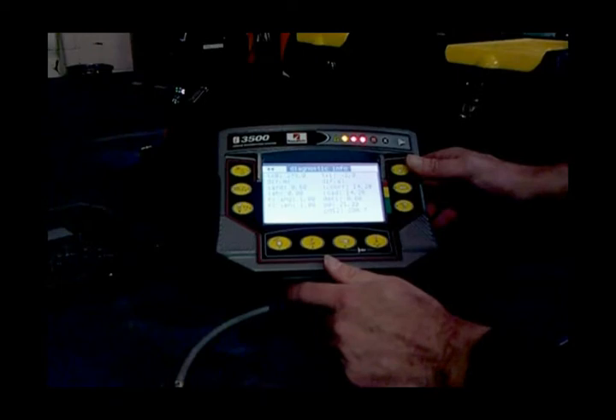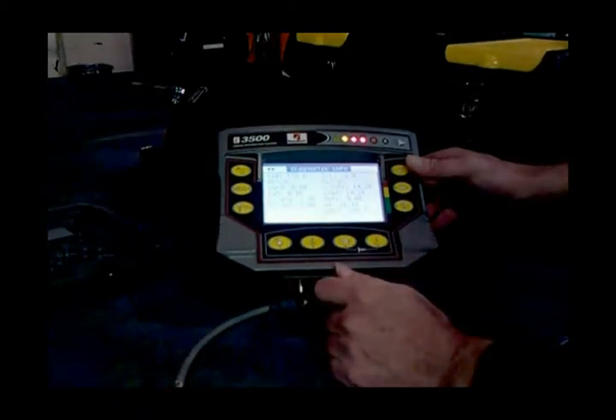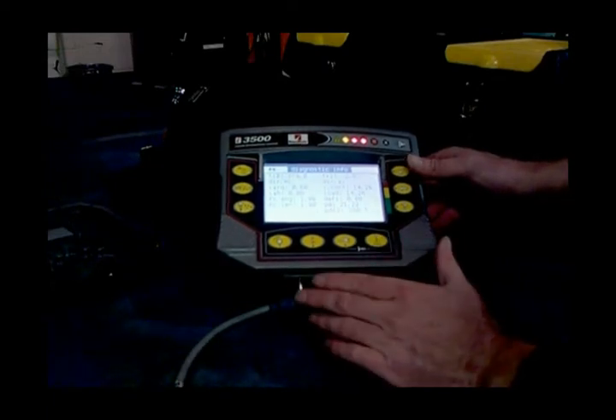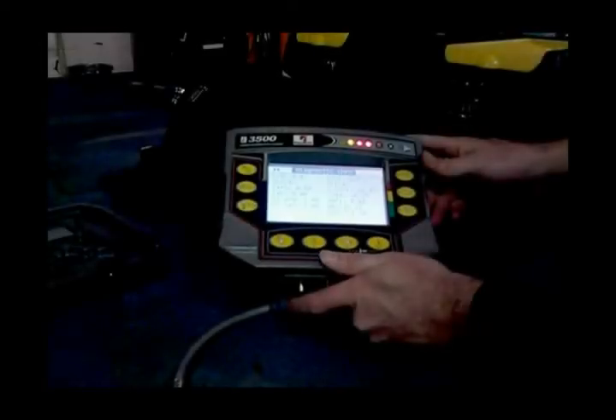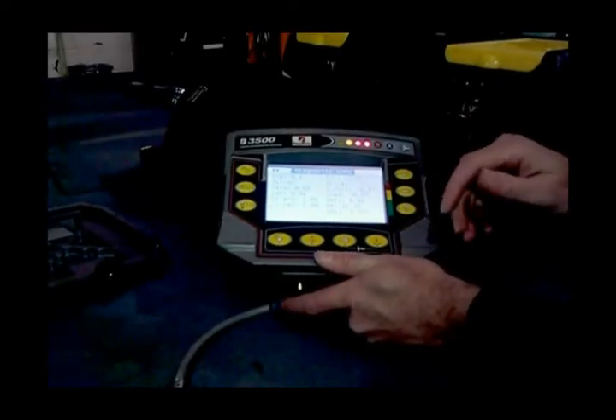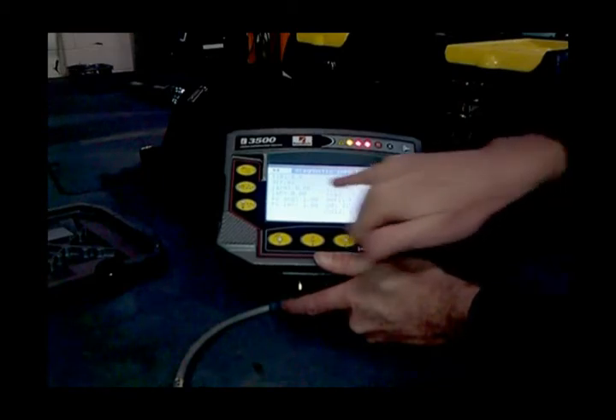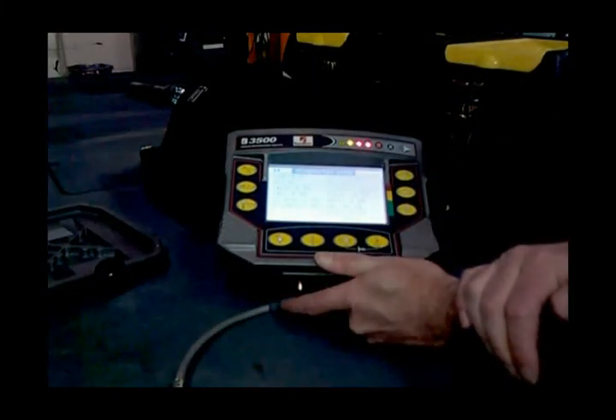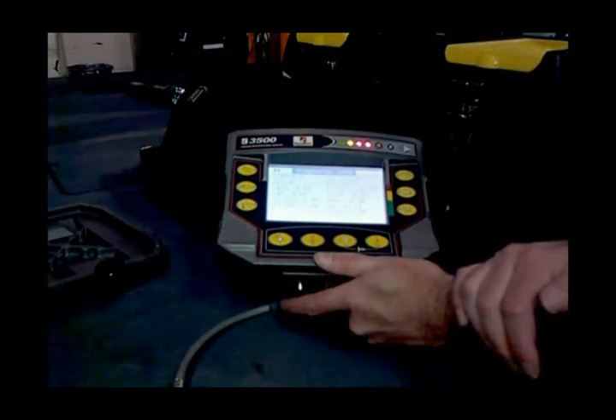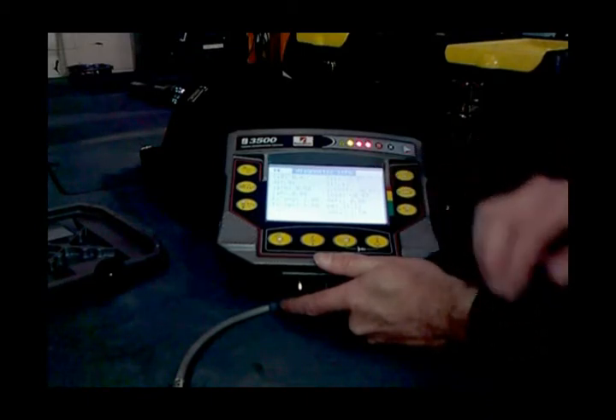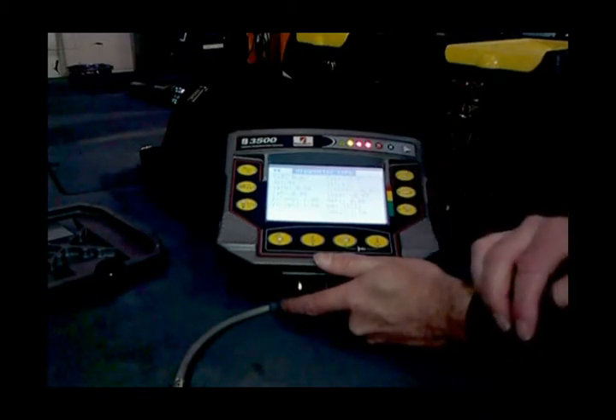Once I turn off the calibration switch in the transducer box, that should go to 0.0 to 3.0. I'm going to go ahead and do that, and we can see what we have afterwards. All right, I have turned off the calibration switch in the transducer box, and TX0 is now down to 0.0, which is where it should be. Now we need to do the same thing for the TX1 side.